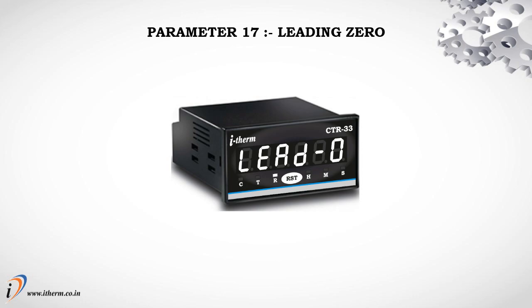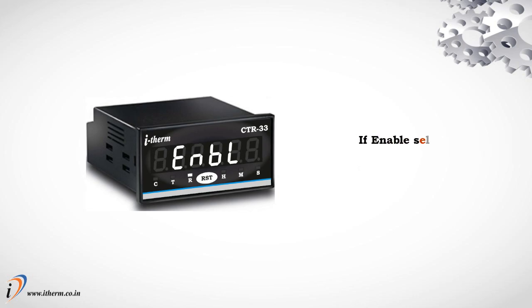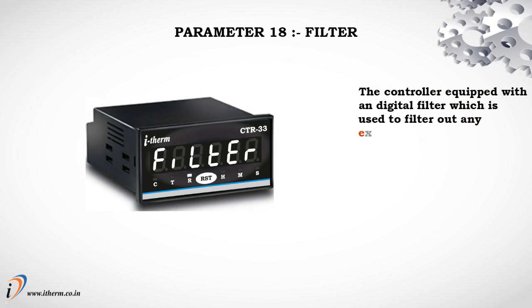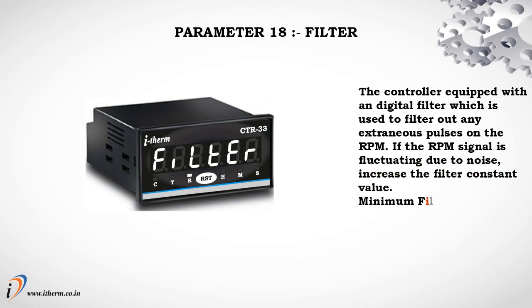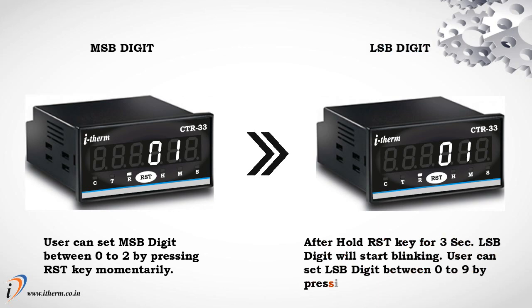Parameter 17: Leading Zero. If disabled, leading zeros will not display in run mode. Parameter 18: Filter. The controller is equipped with a digital filter used to filter out extraneous pulses on the RPM signal. If the RPM signal is fluctuating due to noise, increase the filter constant value. The minimum filter value is 1 and the maximum is 20. The user can set the MSB digit between 0 to 2 by pressing the reset key momentarily. After holding the reset key for 3 seconds, the LSB digit will start blinking and can be set between 0 to 9.